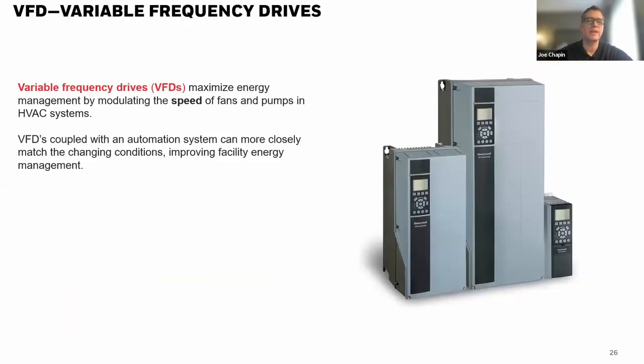So that's another part of the energy savings strategy: modulate the fan speed of these devices and couple it with a building automation system to match changing conditions. In a lot of cases, you don't need 100% fan capacity; sometimes 25 to 30% will do. Over time, running fans at only 25% capacity really stacks up the energy savings. VFDs are a key part of the strategy, and they're also connected to the BMS system.